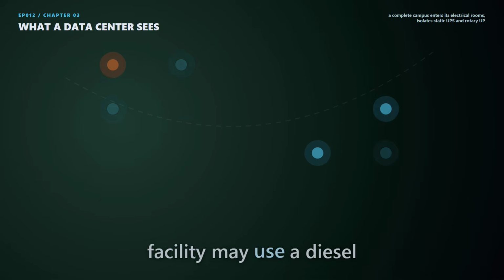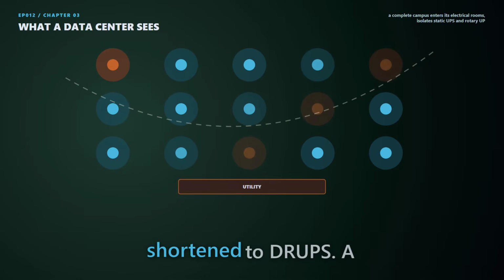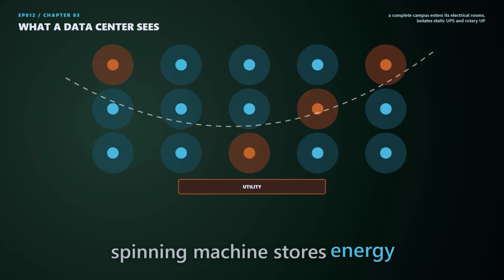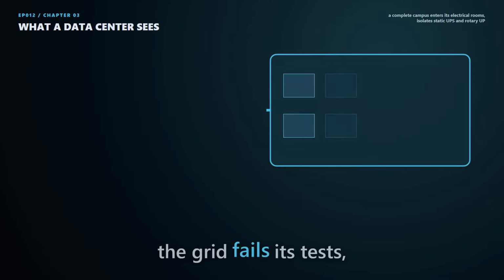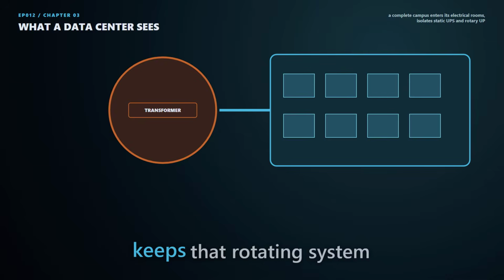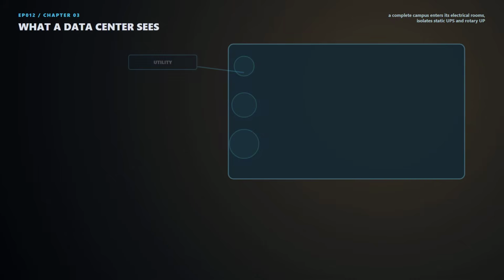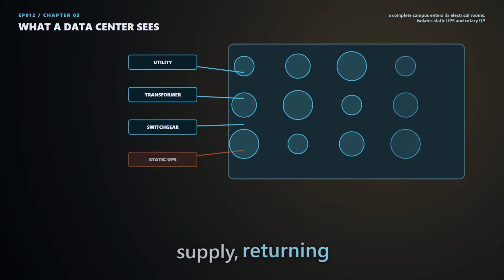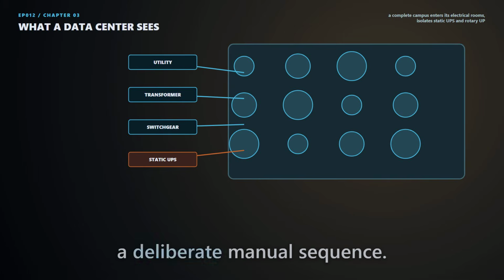Another facility may use a diesel rotary UPS, often shortened to DRUPS. A spinning machine stores energy in a flywheel. If the grid fails its tests, an engine takes over and keeps that rotating system alive. Once the facility has committed to that alternate supply, returning to the grid may require a deliberate manual sequence.